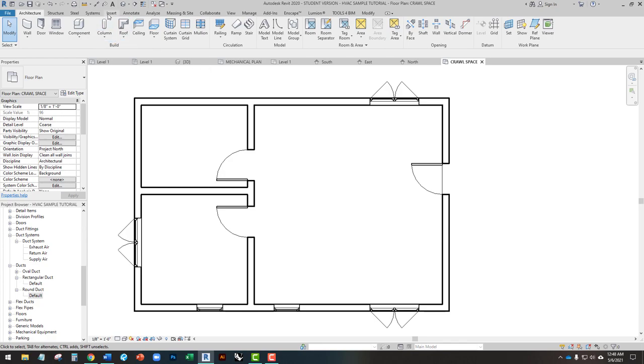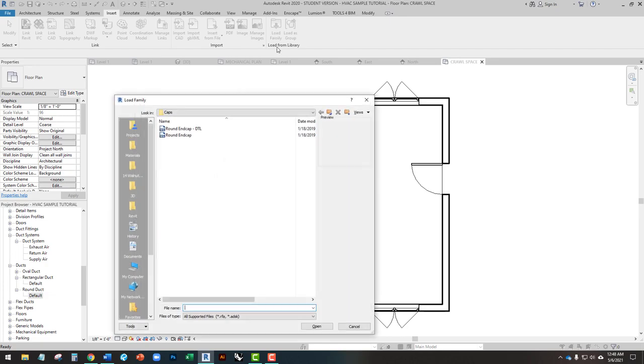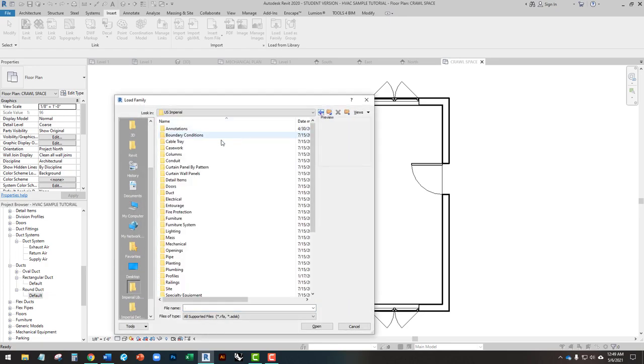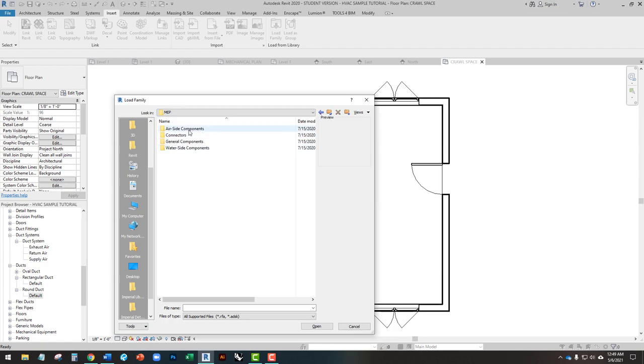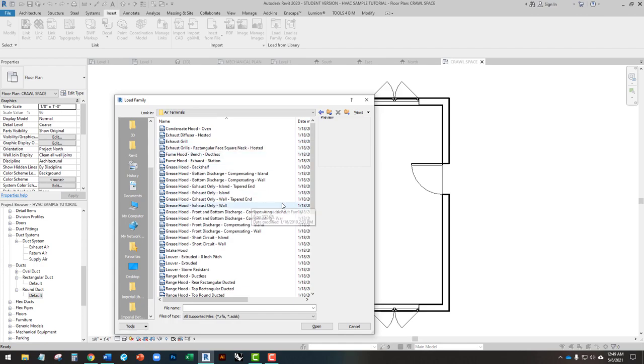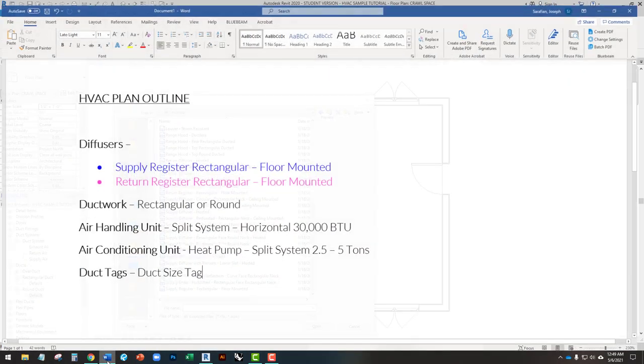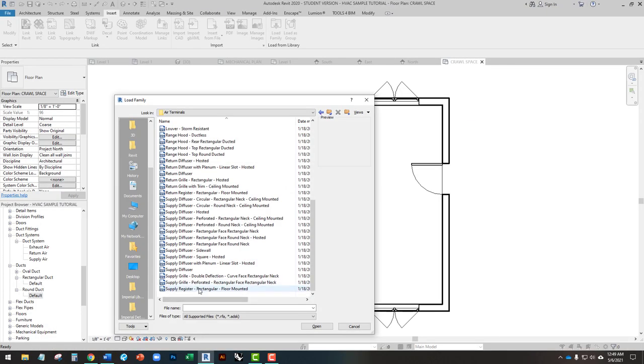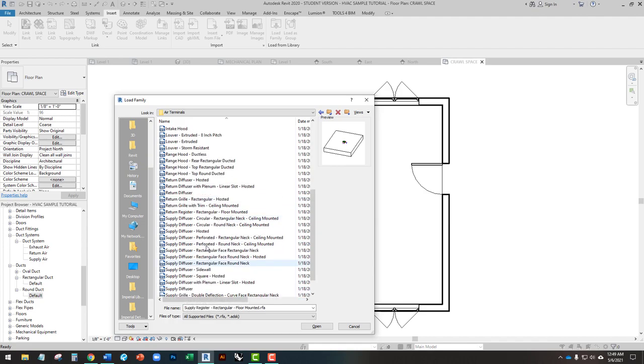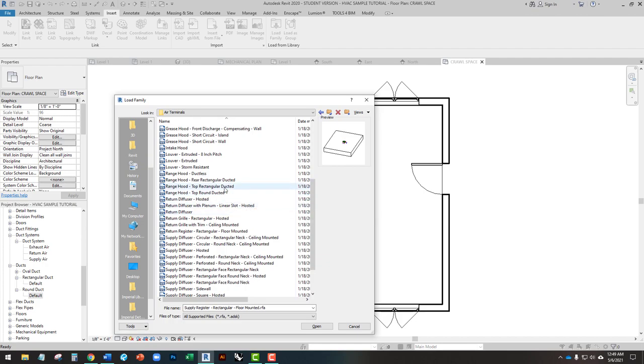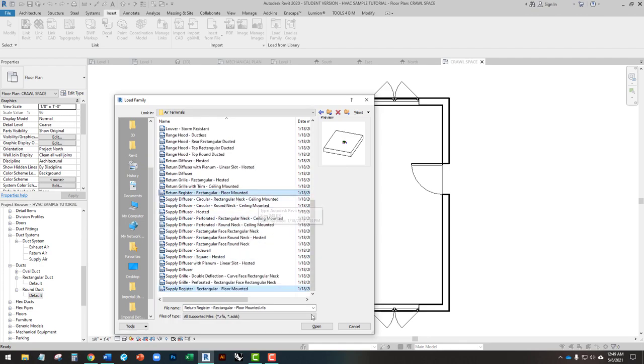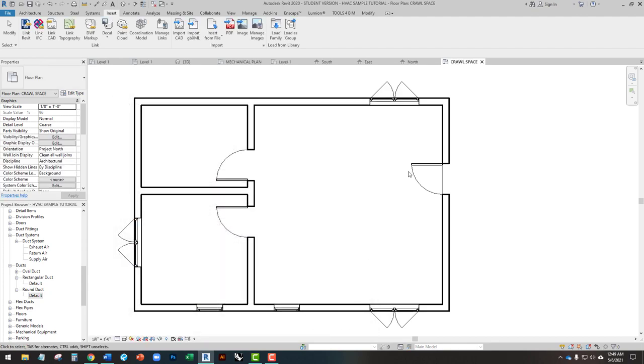I'm going to go to Insert > Load Family, starting in US Imperial, then navigate to Mechanical > MEP > Air Side Components > Air Terminals. We're going to find both a Supply Register Rectangular floor-mounted and a Return Register floor-mounted as well. I hold Control and select both of these, so this will give us both a supply register and a return register. I'll open those — now they're loaded into the file.